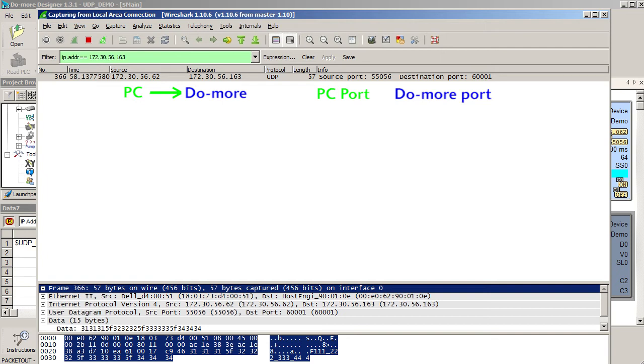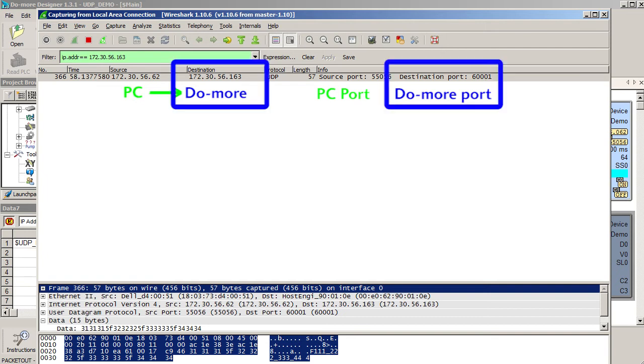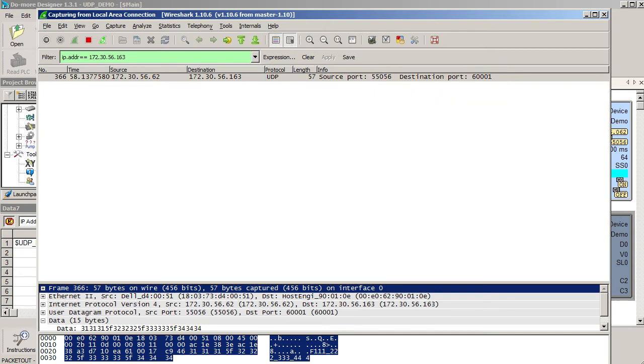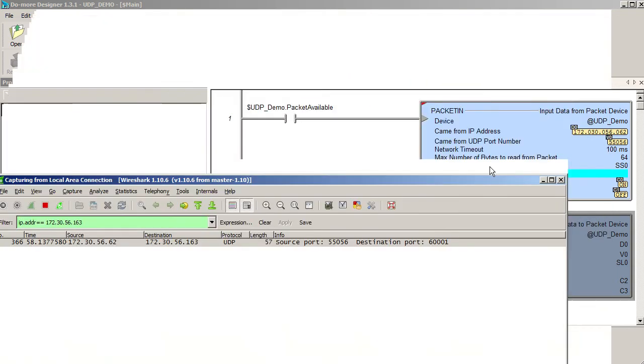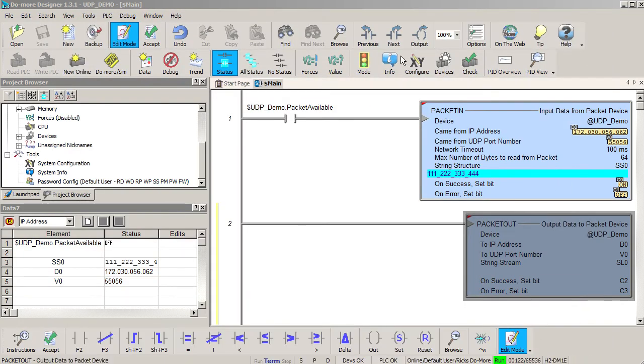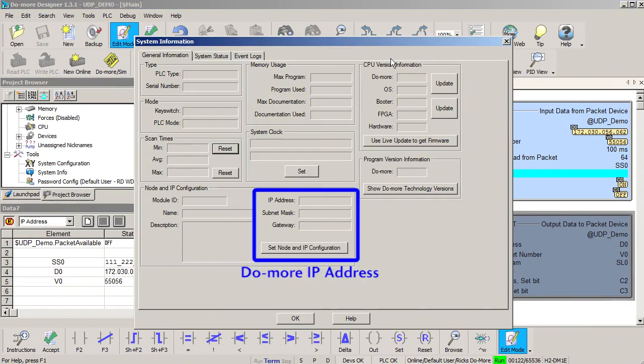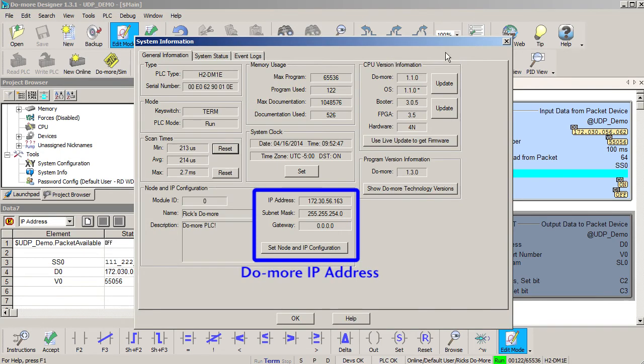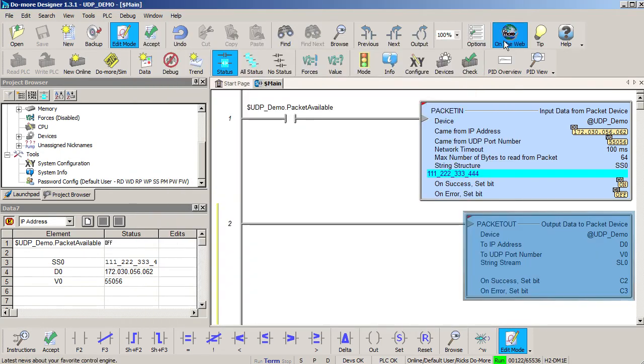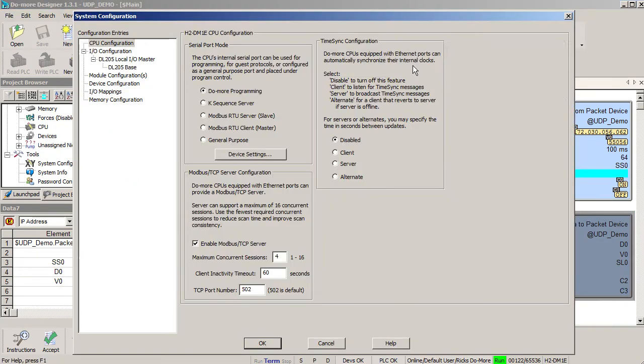Usually if a message isn't received, the destination IP address or the UDP port number don't match what the do-more is expecting. You just need to make sure the do-more project matches these numbers. As a reminder, the do-more's IP address is here under the info button and the UDP port is here under the configure button.